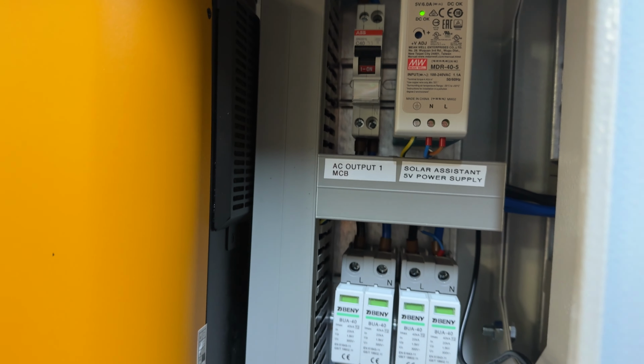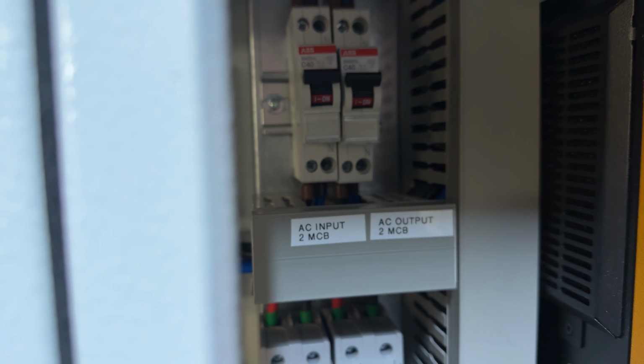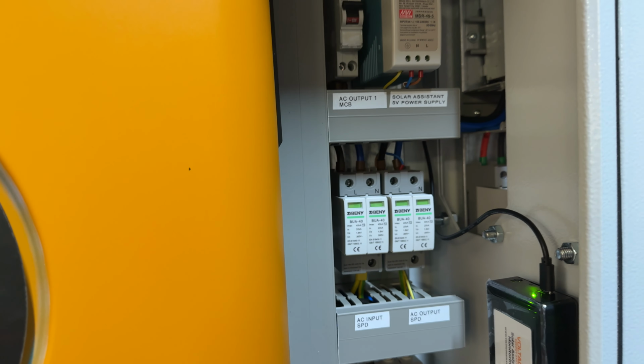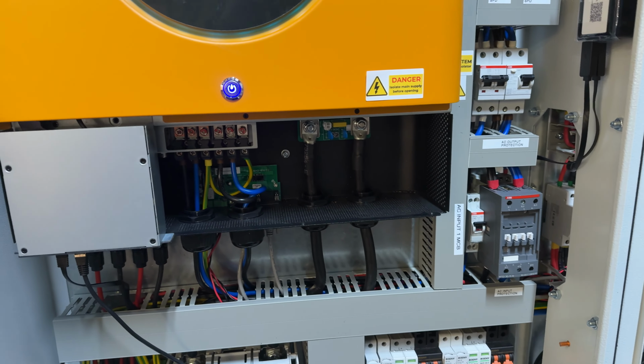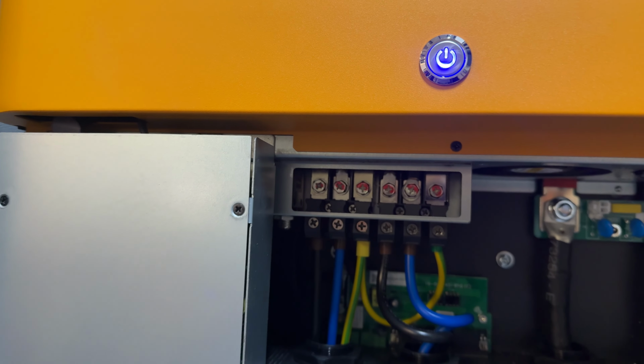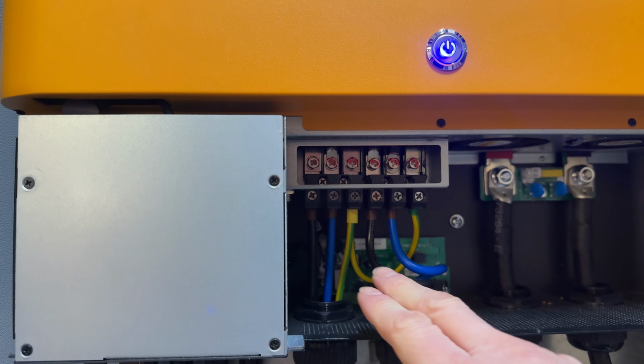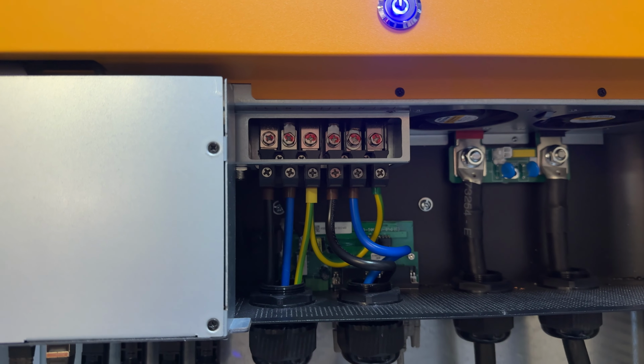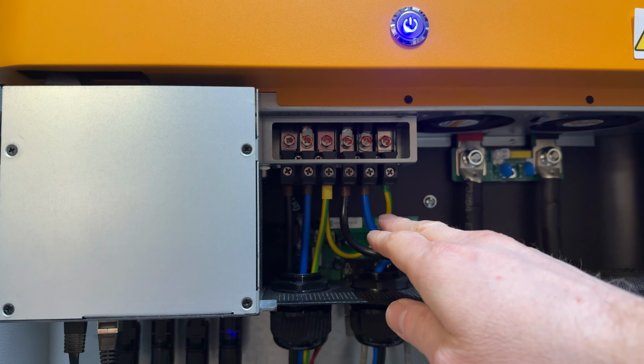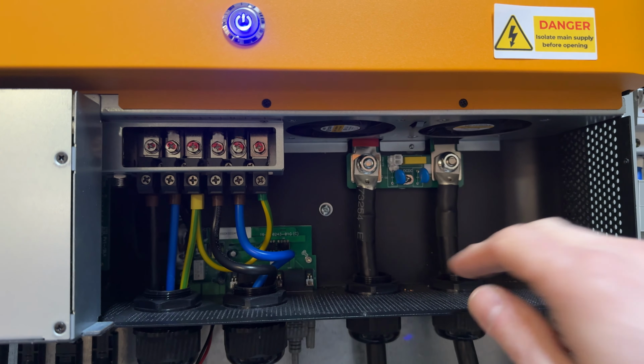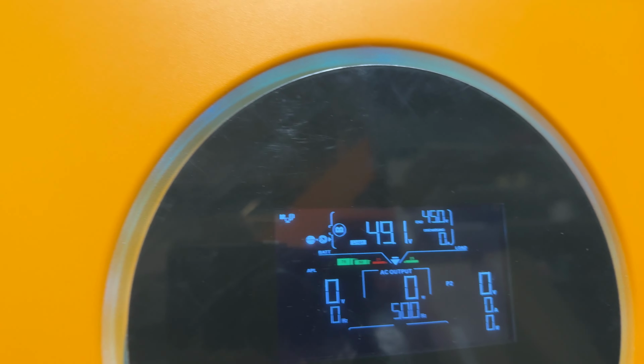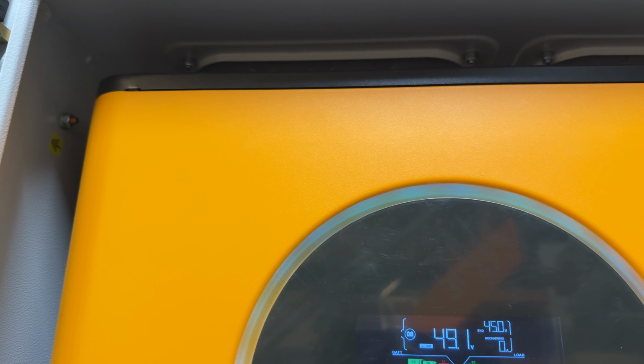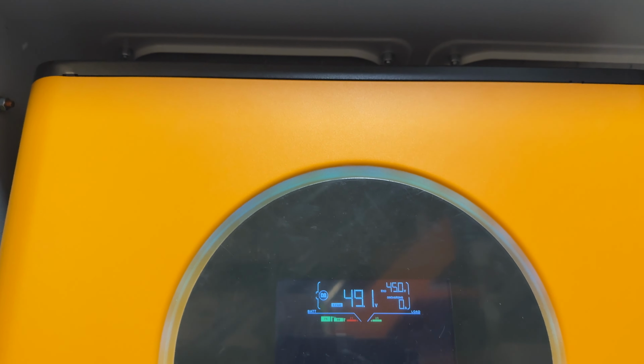And at this point, this is the AC output MCB 40 amps, and the AC output number 2, another 40 amps from the secondary inverter. That's the AC input of the first inverter and the AC input of the secondary inverter. This is how we wired the inverters internally. You don't have to change any of the cables. They are all fixed. There is no need to alter any wiring. That's the incoming power supply, and that's the output, AC input, AC output, battery terminals, and that's our nice touch screen here. You can set the menu in the master and the slave inverter.